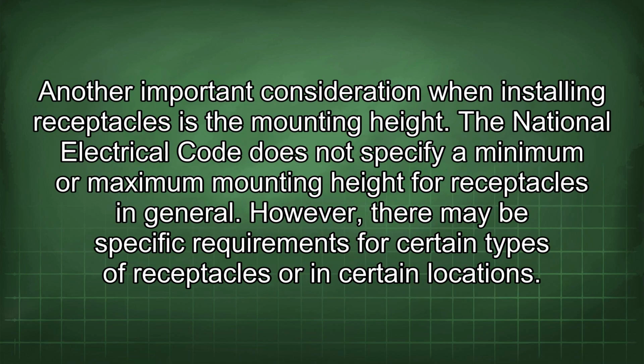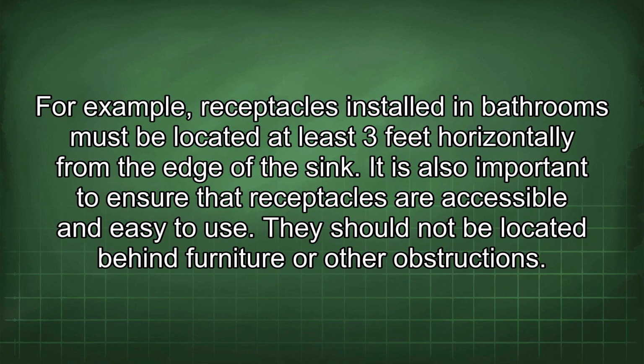Another important consideration when installing receptacles is the mounting height. The National Electrical Code does not specify a minimum or maximum mounting height for receptacles in general. However, there may be specific requirements for certain types of receptacles or in certain locations. For example, receptacles installed in bathrooms must be located at least 3 feet horizontally from the edge of the sink.